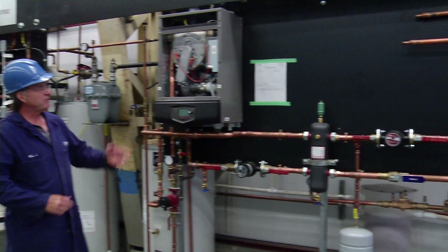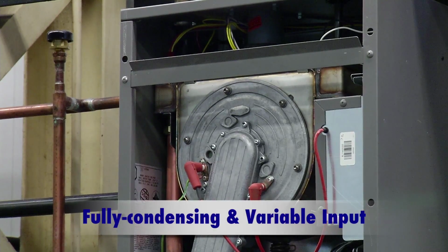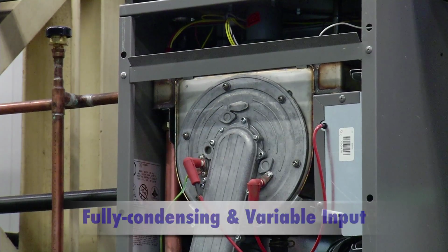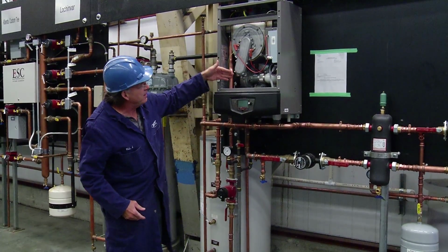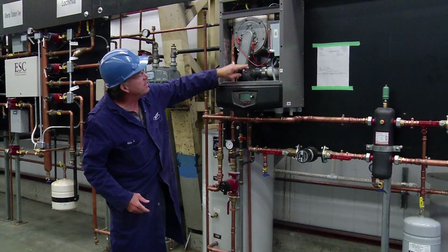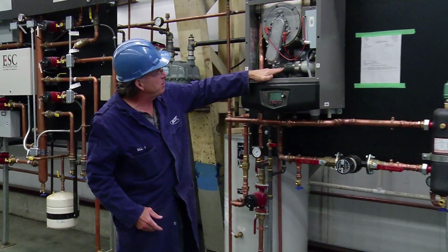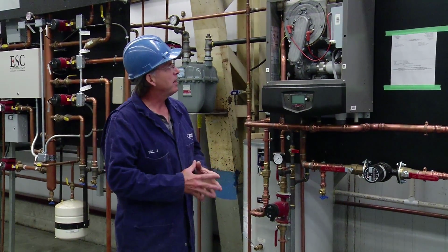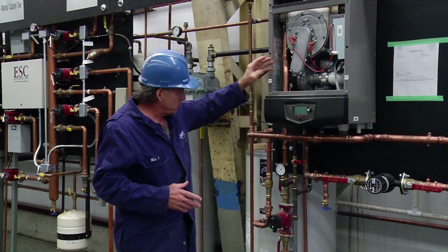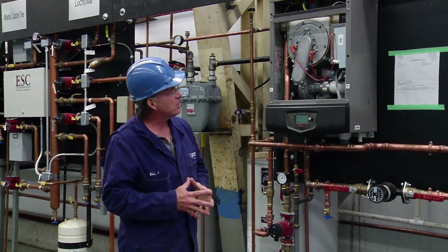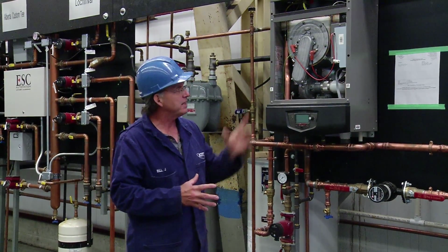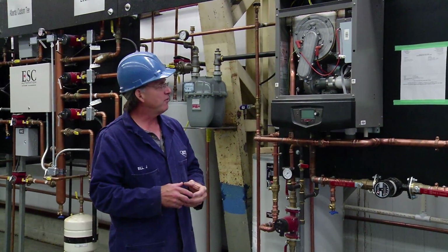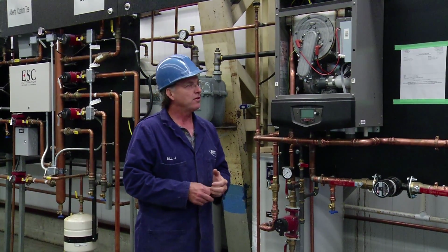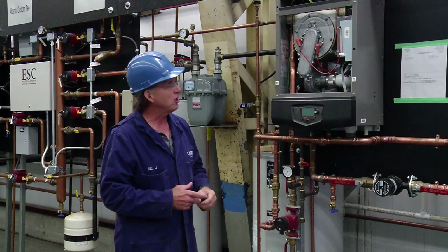Here's another example of a boiler that is fully condensing and fully variable input. You can see that it has the fan that drives air from the outside supply source through a heat exchanger, and that's where it's lit off. It also has to have condensation piping because it will fully condense the vent gases, therefore recovering all that latent heat that we normally lost a few decades ago.